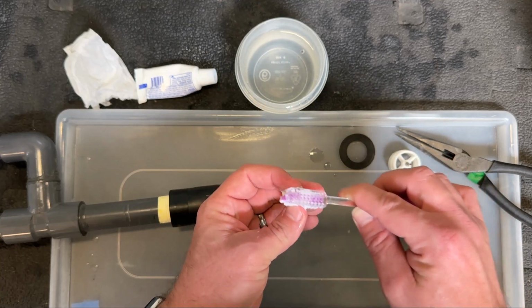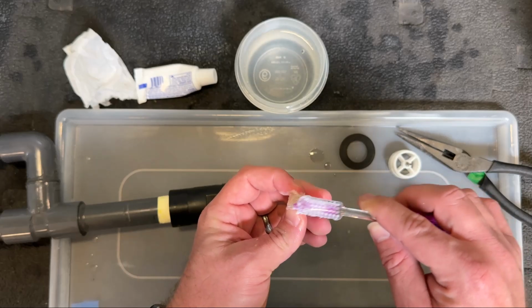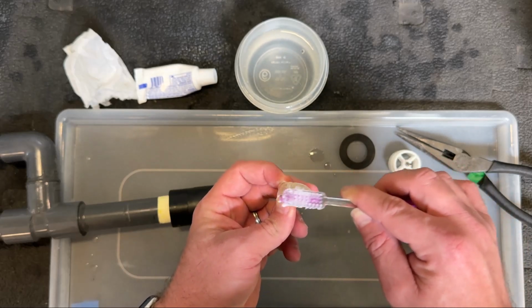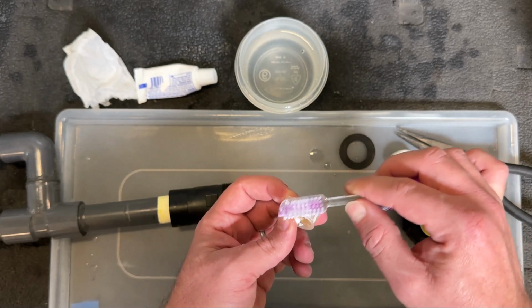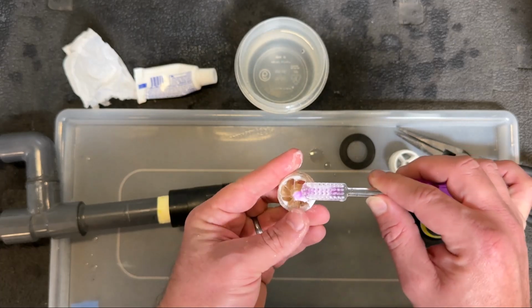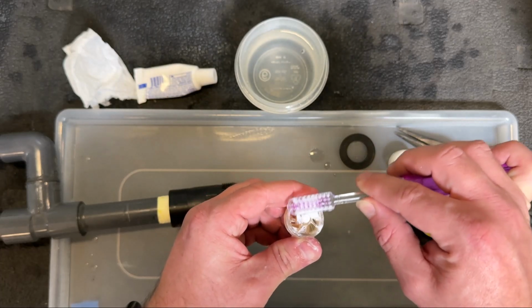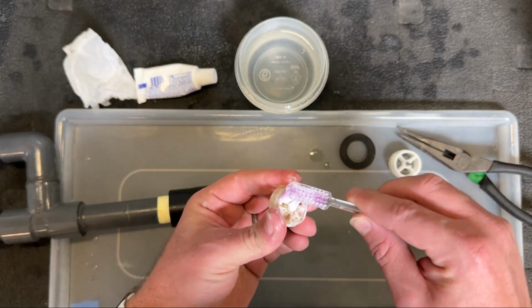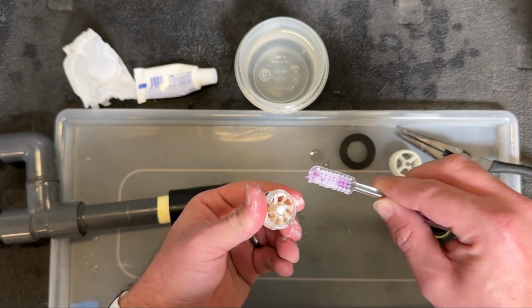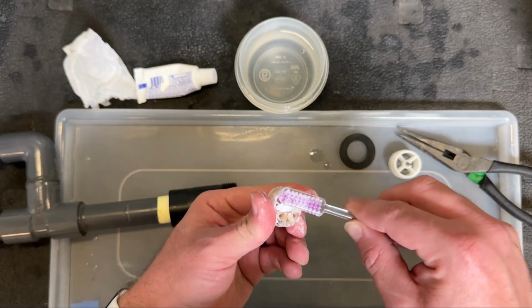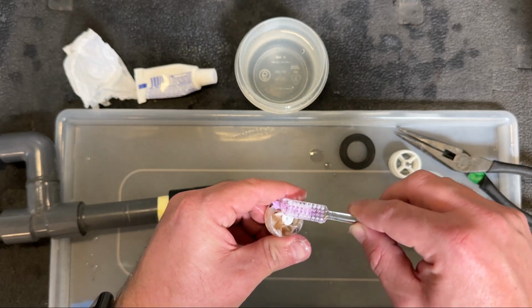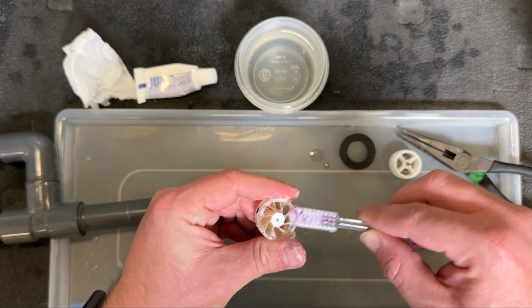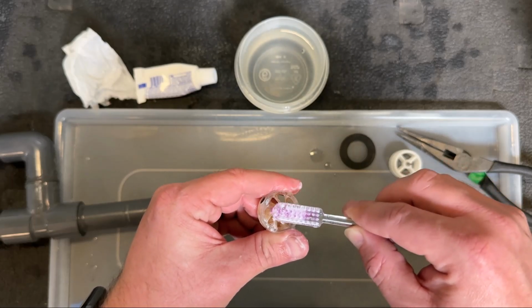We're trying to knock free any debris and remove any grime that's built up on the impeller. It's important to clean inside the impeller blades, as grime and debris can build up on them as well.